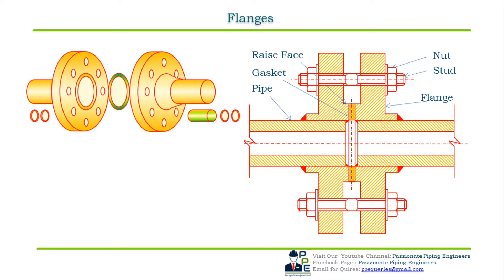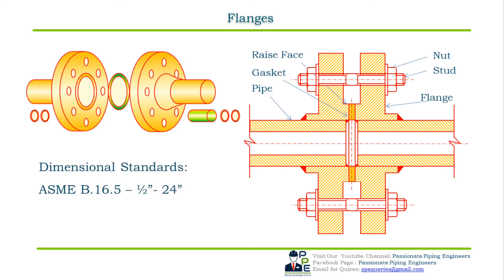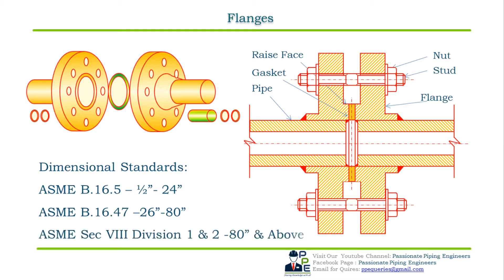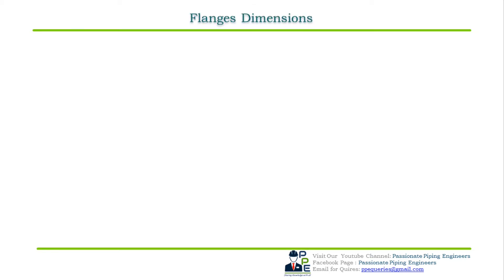Flange joints are made by bolting together two flanges with a gasket between them to provide a seal for a leak-proof joint, as shown in the adjacent figure which shows the cross-sectional view of the flange joint assembly with gaskets and stud bolts. Dimensional standards for flanges are ASME B16.5 for sizes from 0.5 inch NPS to 24 inch NPS, ASME B16.47 for sizes from 26 inch NPS to 80 inch NPS, and ASME Section 8 Division 1 and 2 for sizes 80 inch NPS and above.